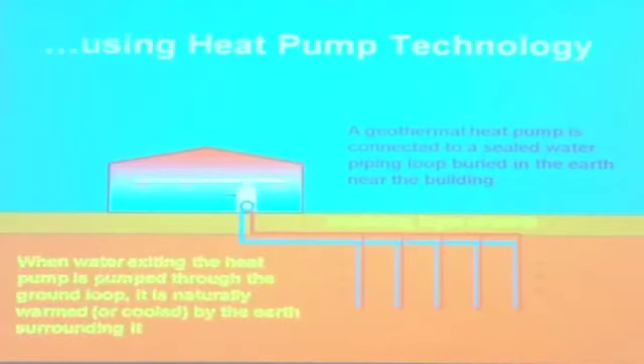So the geothermal heat pump is using all this land. You bring the water, you see the water circulating into a geothermal unit. I'll show you a whole bunch of different kinds of units. You see the ductwork comes off the top. So in the heating mode, you're pulling the heat out of the water, putting it into an airstream, blowing it through your ducts, and it comes out the grills just like your current system does in your house or any other building. And in the cooling season, you pull the heat out of the air, so cold air comes out the grill, and heat goes down in the ground, transferred into that water and carried to the soils.